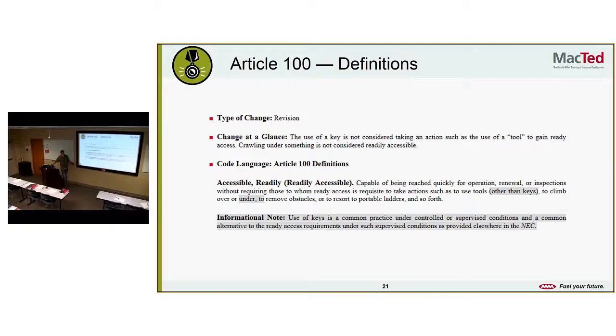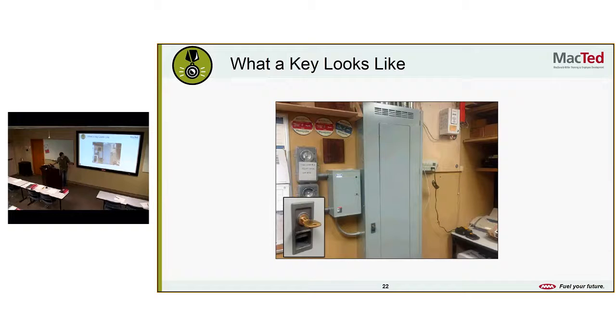Article 100 definitions, they had a revision. Change at a glance: the use of a key is not considered taking an action such as the use of a tool to gain readily accessible access. Crawling under something is not considered readily accessible. This came about because with a breaker panel, you have to have ready access to that. But there were some enforcers saying that a key doesn't provide ready access to the panel, when in fact it does. I mean, a key is not really a tool, so they just clarified that. So a key is not a tool. Having something locked is still readily accessible, but you can't crawl underneath like a beam or something. So here's a picture of that, in case you didn't know what a key looked like.